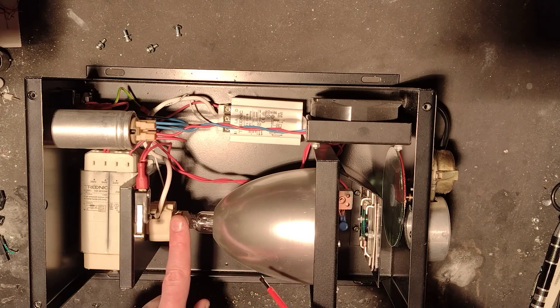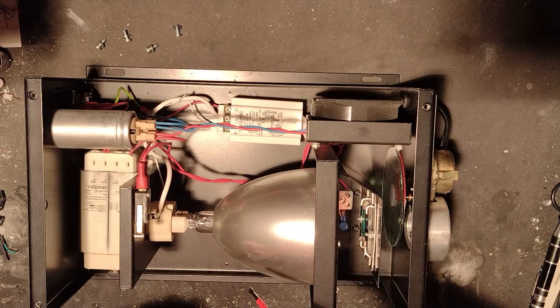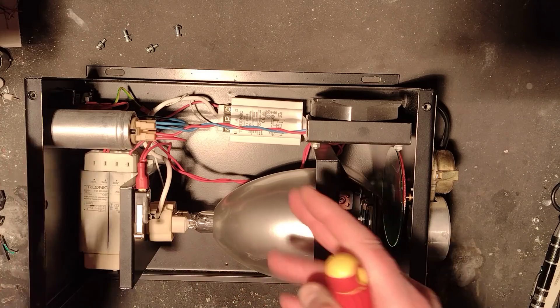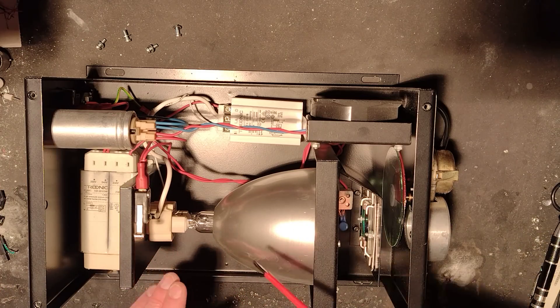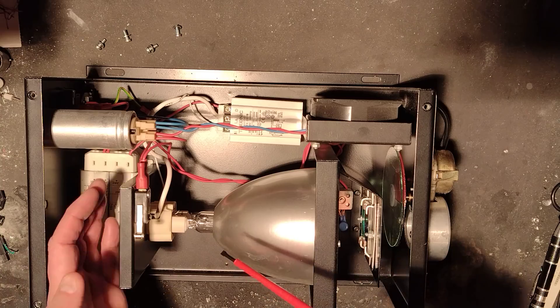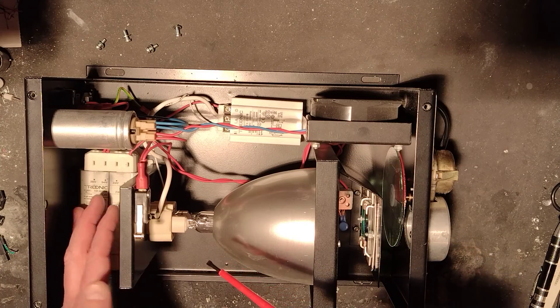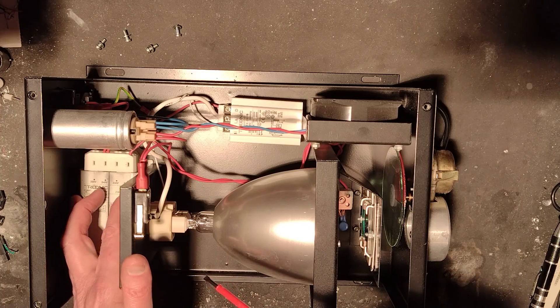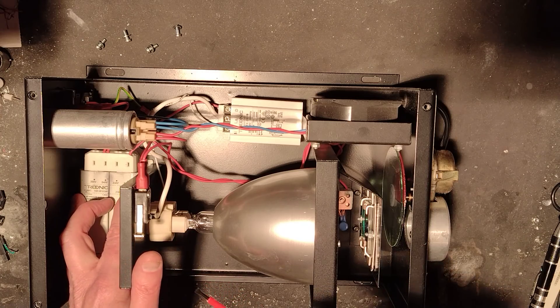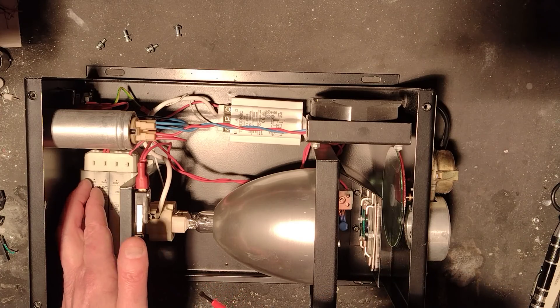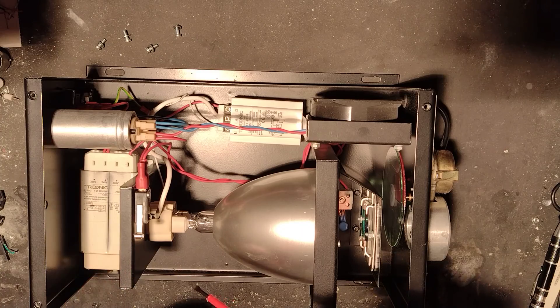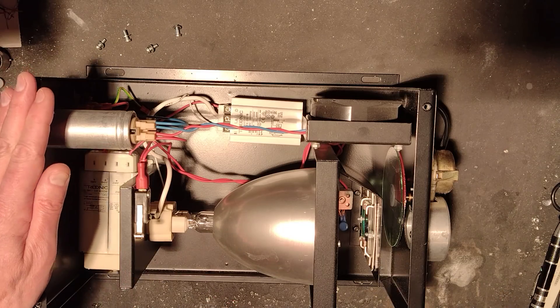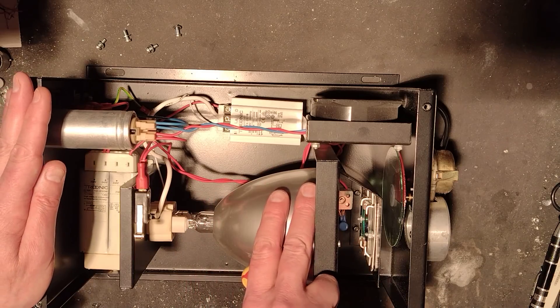This is going to be super red hot. It is red hot. I shall take that out and show you afterwards, but I'll let it cool down first. But that then ignites the lamp. And then it's strictly down to the current limiting of this ballast. The ballast has four connections. It's got the common connection, 230, 240 and 250 volt taps. It's in the 240 volt tap, reasonable enough.